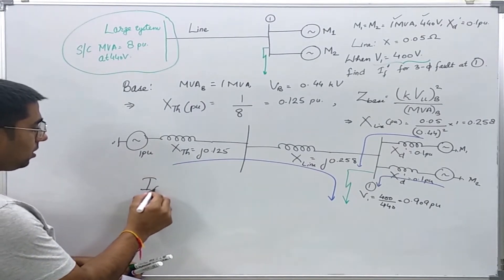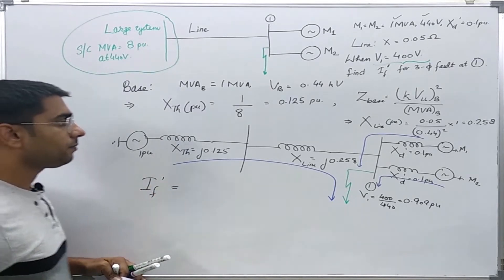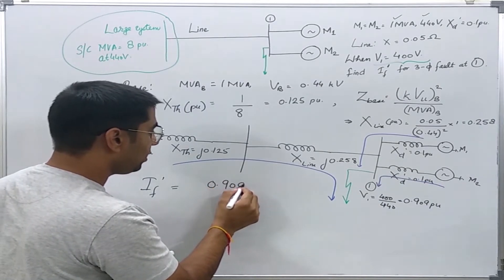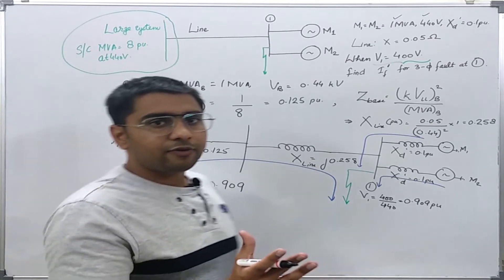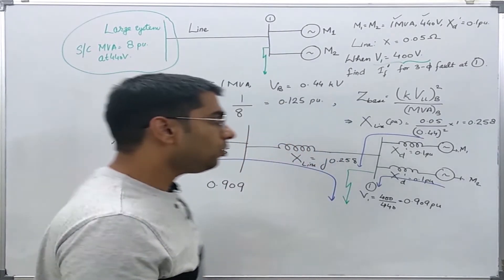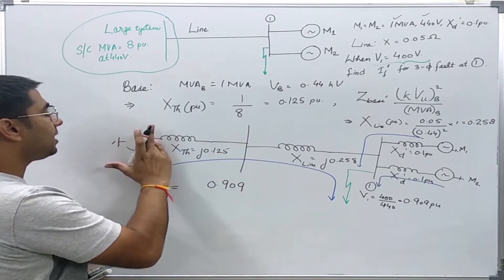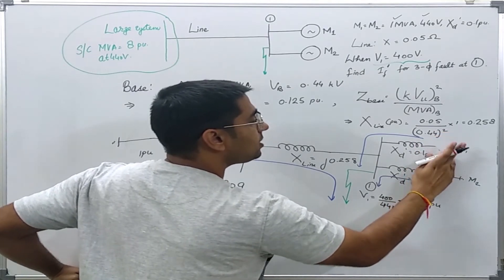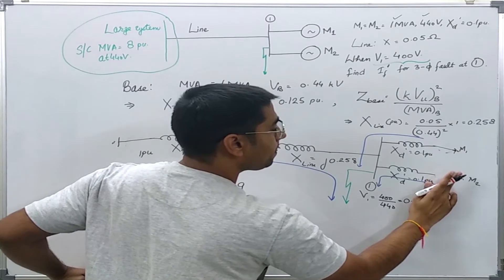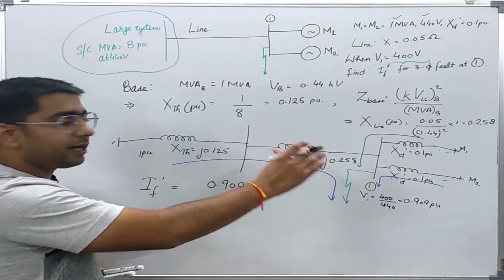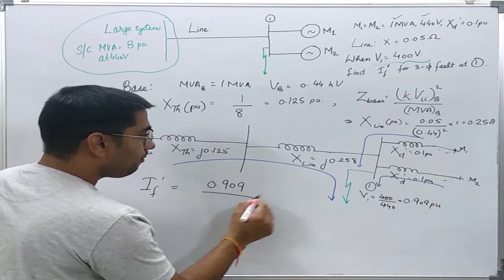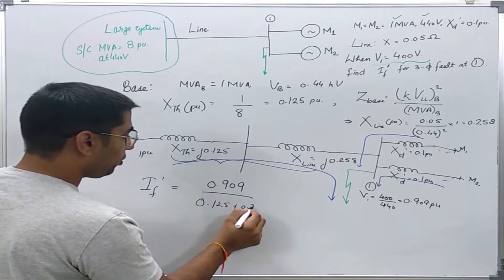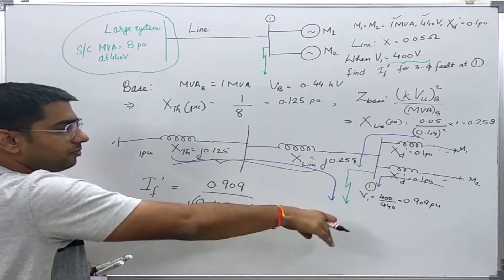Using the Thevenin method, deactivating all other sources, the fault current IF' is found from the pre-fault voltage of 0.909 per unit. The contribution from the power system side is 0.909 divided by (0.125 + 0.258) per unit.